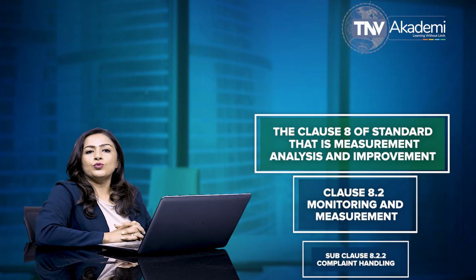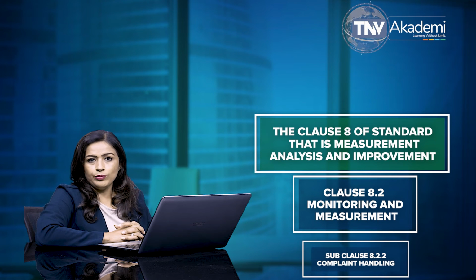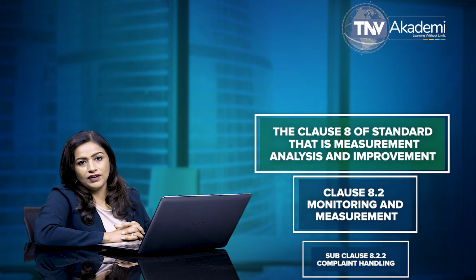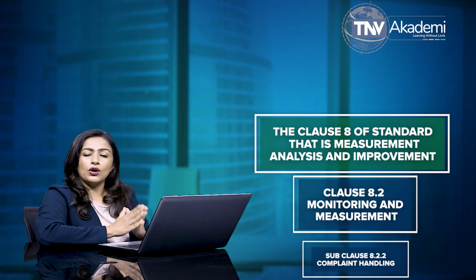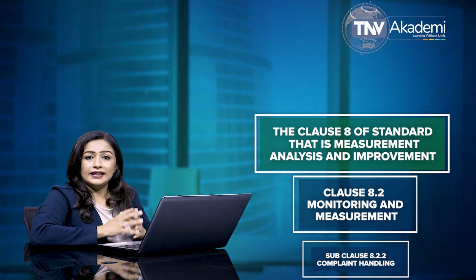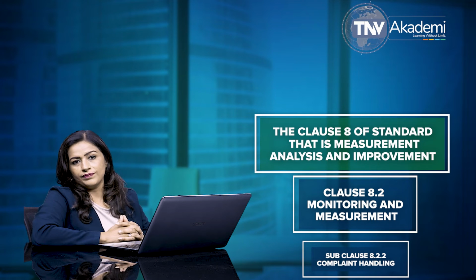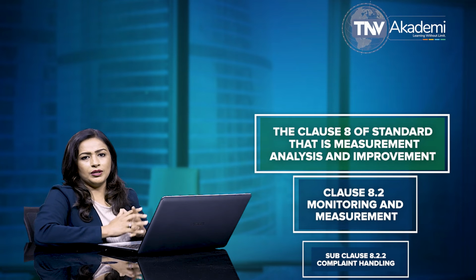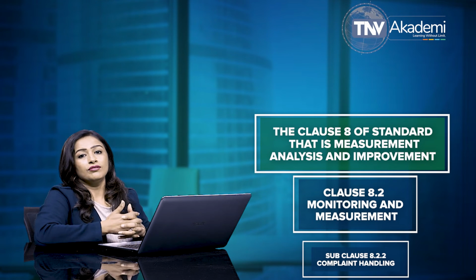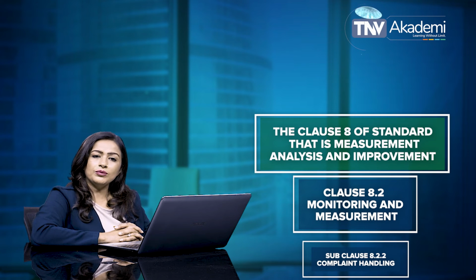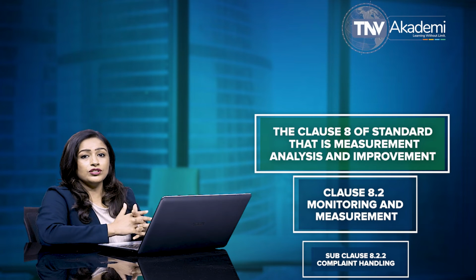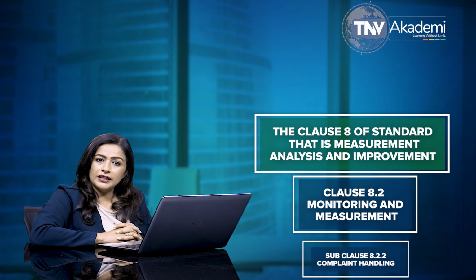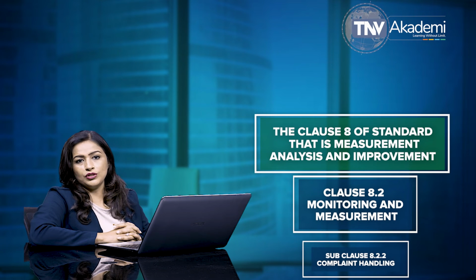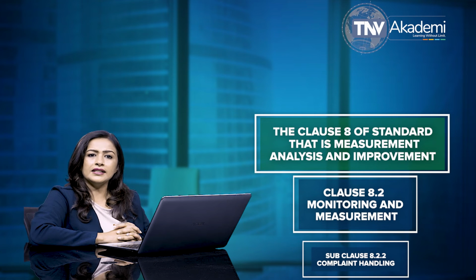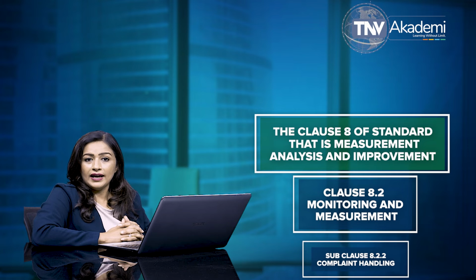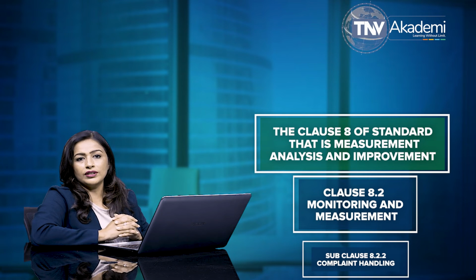Let's talk about 8.2.2, complaint handling. This subclause 8.2.2 of ISO 13485 states that the organization is required to document procedures for timely complaint handling in accordance with applicable regulatory requirements. These procedures must include, at a minimum, requirements and responsibilities for receiving and recording information, evaluating information to determine if the feedback constitutes a complaint, investigating complaints, determining the need to report the information to the appropriate regulatory authorities, handling of complaint-related product, and determining the need to initiate corrections or corrective actions.